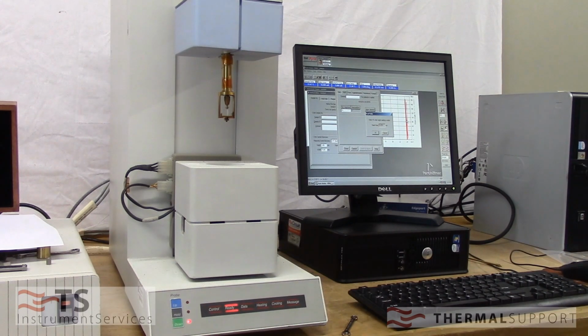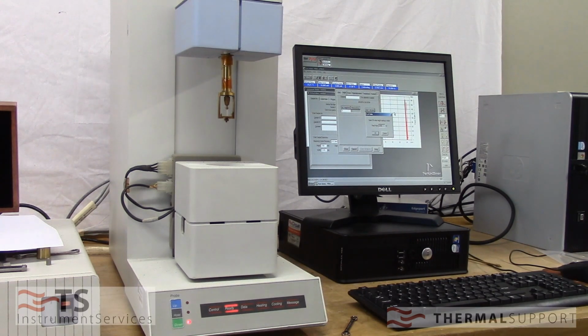And it immediately came back to 10.376. So let's let that sit there for just a minute and see what it comes back to. Okay, it came back, probably within 30 seconds. We let it sit a little bit longer to make sure it wasn't updating. When it came back at 9.997, and now it's 9.996. So we're pretty good there. That's what we would expect after the electronic calibration we've done. So we're going to say OK.